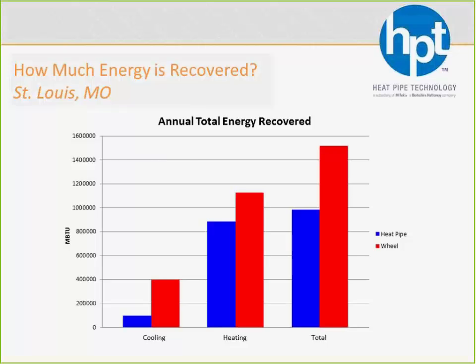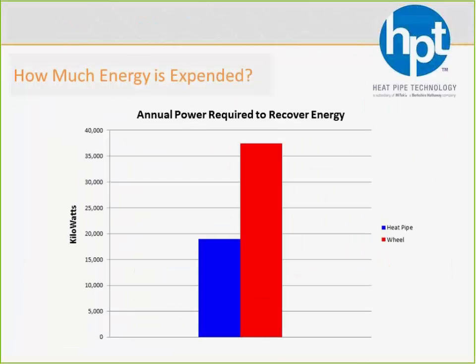So if you looked at the whole year and put all those BTUs together, we're naturally going to recover less BTUs than a wheel does. But if you're looking at the power being added into the system, and take into account that the wheel is adding maybe twice as much static than we are, but also has a motor to keep it turning, and you also have to add more air to it to overcome leaks and purge and stuff like that, you actually find that a wheel may require twice as much power to operate.